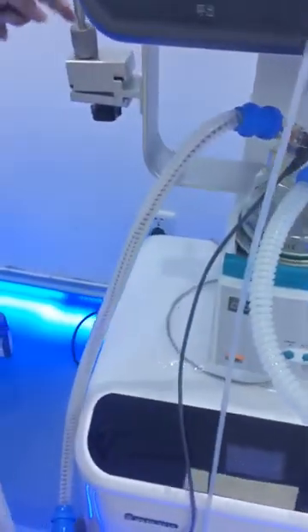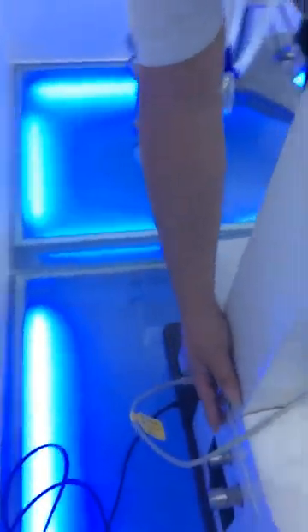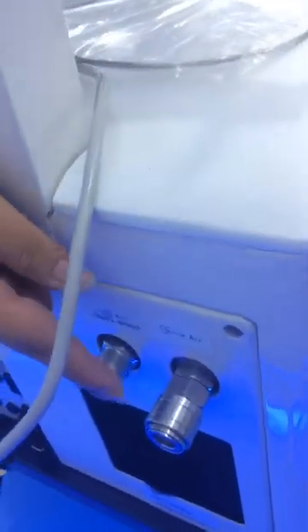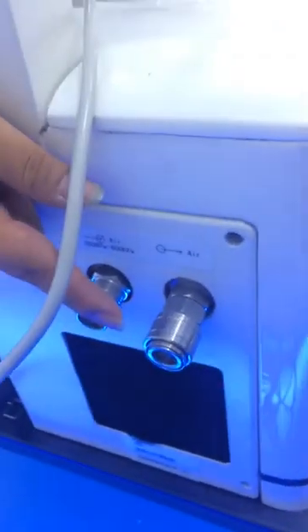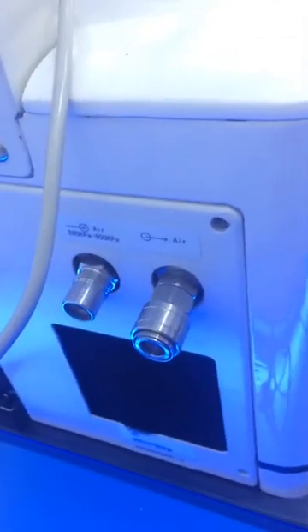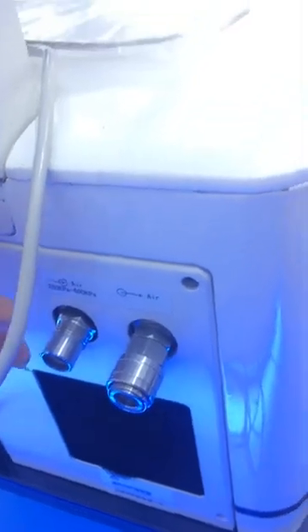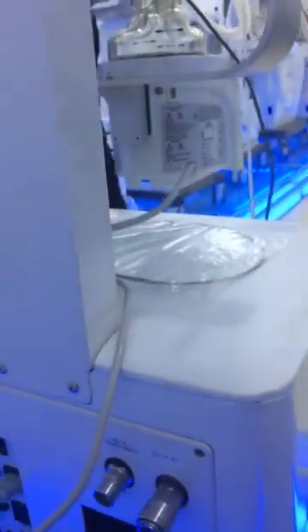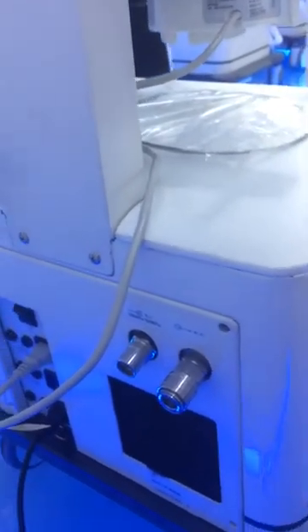And also on the back side of the air compressor, we can see there are 2 parts. One part connects the pipeline with the main pipeline to supply medical air. And we have another one to connect with the central air supply. So if your hospital has a central air supply, we can connect both pipelines. Then it will automatically test whether the central air supply has failed. If it fails, our compressor will automatically start. And if the central air supply recovers, our air compressor will stop.